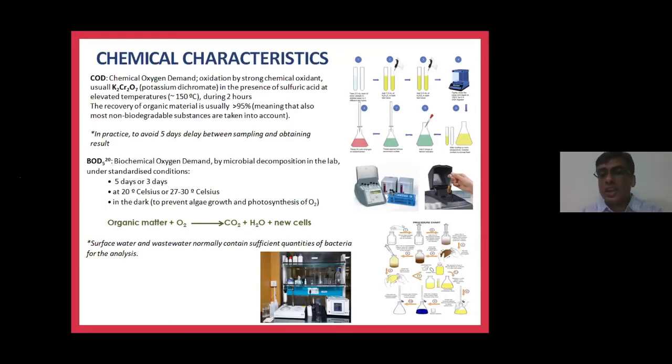Similarly, biological oxygen demand, as we were discussing, is a 3-day or a 5-day process. Right now there are instruments available in our country, and of course approved by the Central Pollution Control Board, CPCB, which are biosensor based, where a particular biosensor reads the biological oxygen demand in the water, and by an algorithm will tell you in a span of 25 to 40 minutes what the biological oxygen demand would be. So instead of spending 3 or 5 days, you get your results within 40-45 minutes. There are instruments like that.